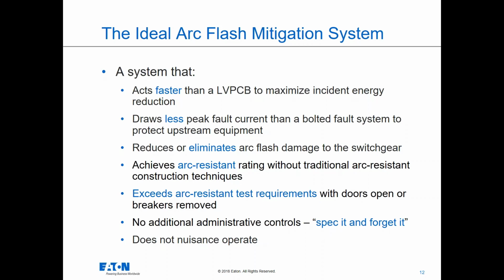You would want something to reduce or eliminate arc flash damage to the switchgear. If I can operate so fast that my incident energy is negligible, then maybe the physical damage to the equipment could be negligible as well. And then once I've removed the source of the fault, I can go right back to operating. I know for a lot of data center folks, hospital folks, process folks, that would be ideal, right?